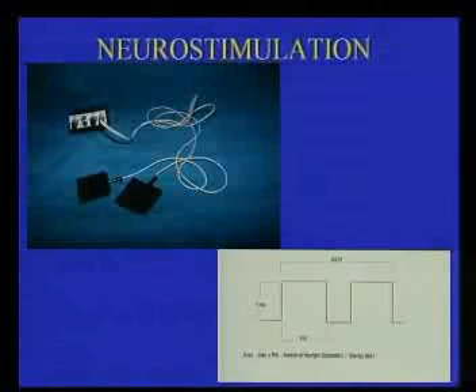Let us have a look at the neurostimulation systems. All neurostimulation systems have almost the same components. Some electrodes, in this case, they would be applied on the skin where in pain, and a generator connected to the electrodes with a lead, a cable. We take into account the number of pulses in hertz, the amplitude of the stimulus in volts, and the width of the pulse, which is measured in microseconds.